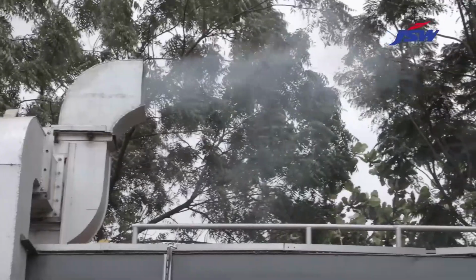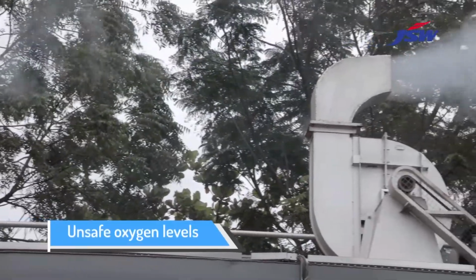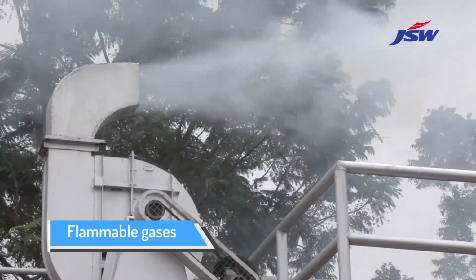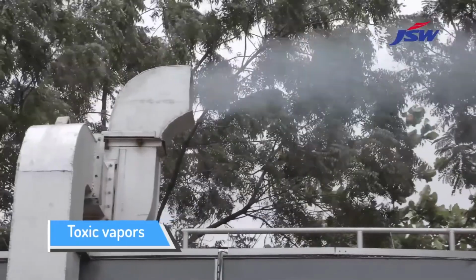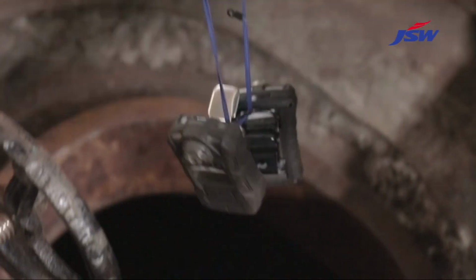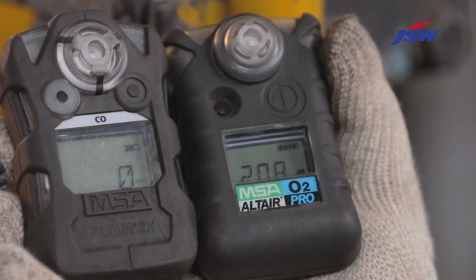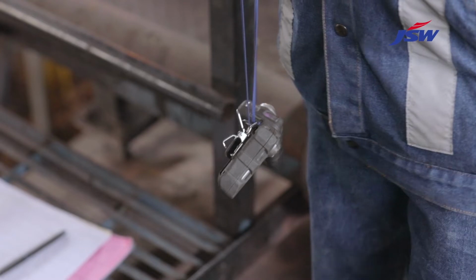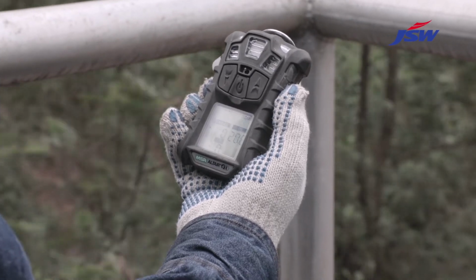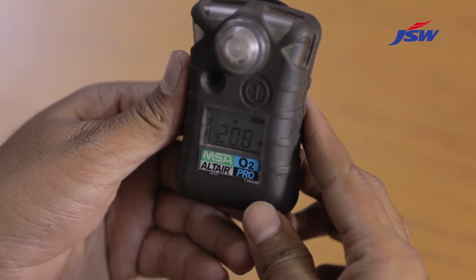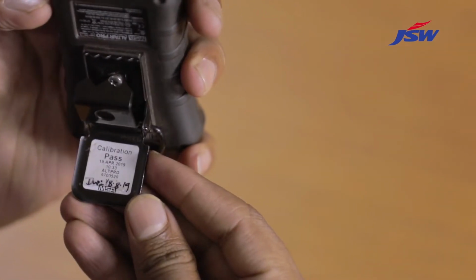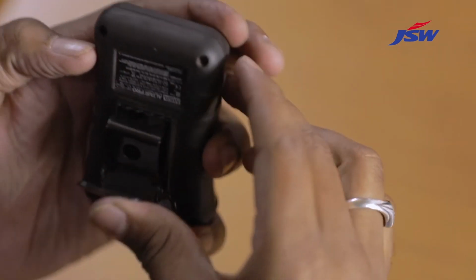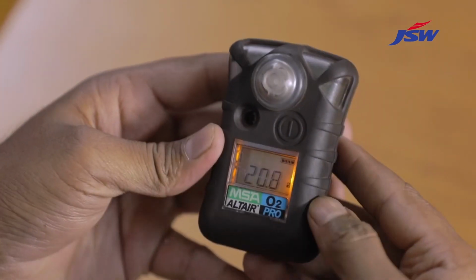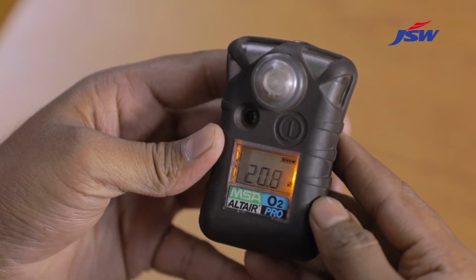Atmospheric testing. When it comes to atmospheric hazards, we are basically looking for three main dangers: unsafe oxygen levels, flammable gases, and toxic vapors. Every confined space must be appropriately tested for the atmospheric hazards with specialized equipment and the procedures. The atmosphere in a confined space should be monitored before and during entry. Instruments used for measuring atmospheric concentrations in confined spaces should have current calibrations. These instruments should be verified on a known source before and after each use.